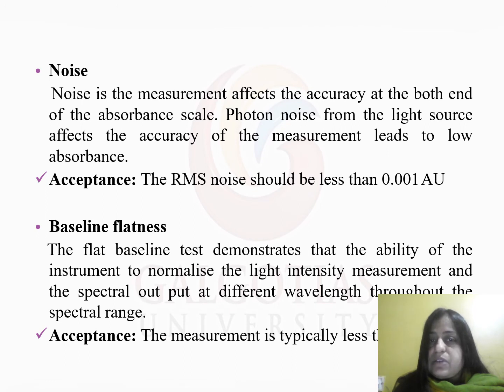260 nanometer should not be greater than 1.5. Noise is a measurement effect on the accuracy at both ends of the absorbance scale. Photon noise from the light source affects the accuracy of the measurement, leading to low absorbance. Acceptance: the RMS noise should be less than 0.001 AU. Baseline flatness: the flat baseline test demonstrates the ability of the instrument to normalize the light intensity measurement and the spectral output at different wavelengths throughout the spectral range. Acceptance: the measurement is typical.